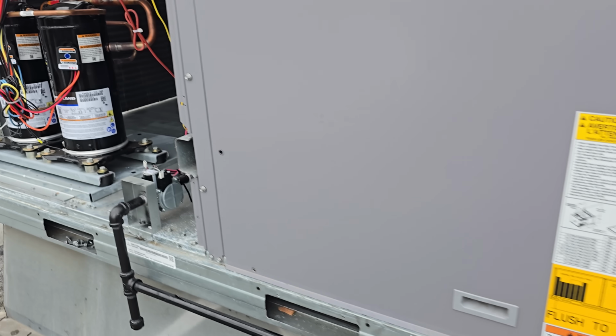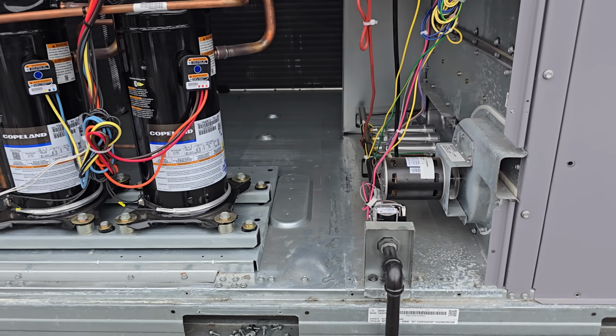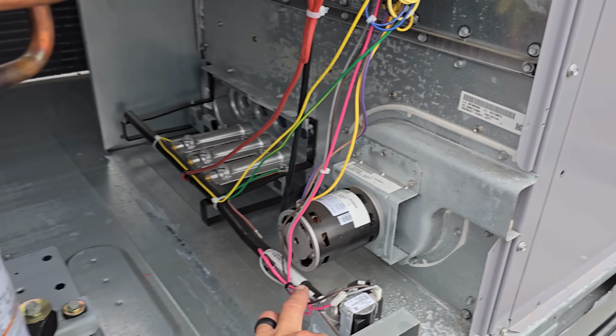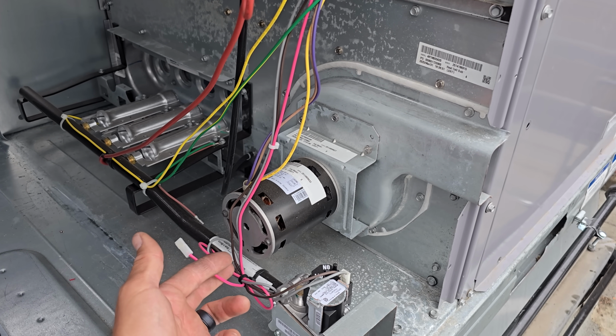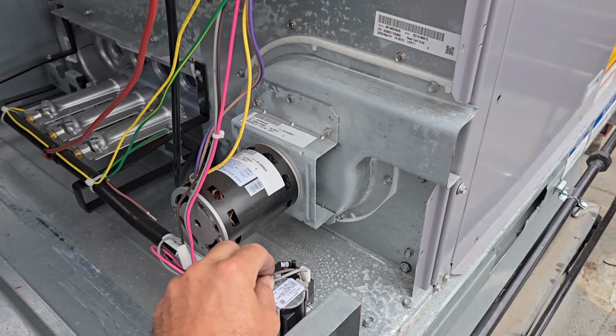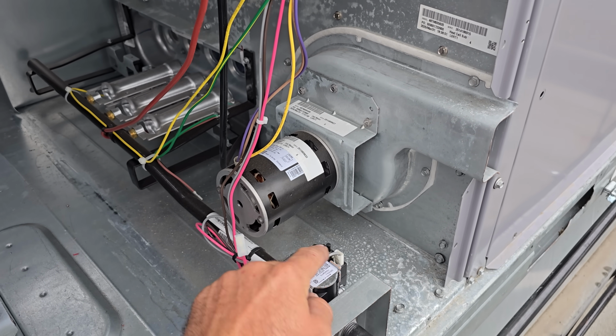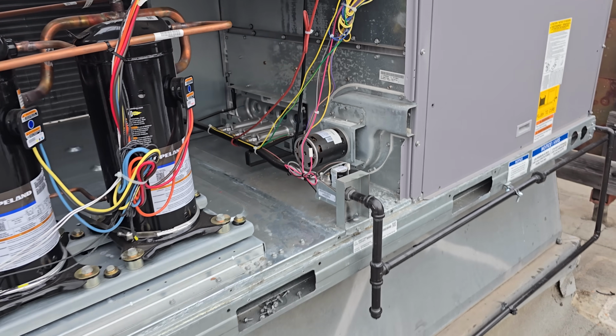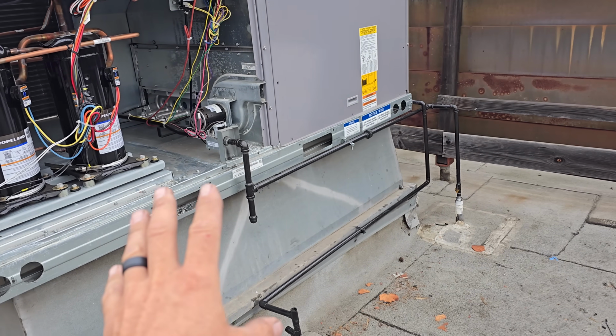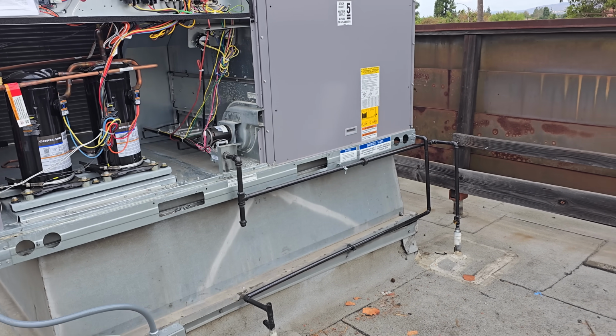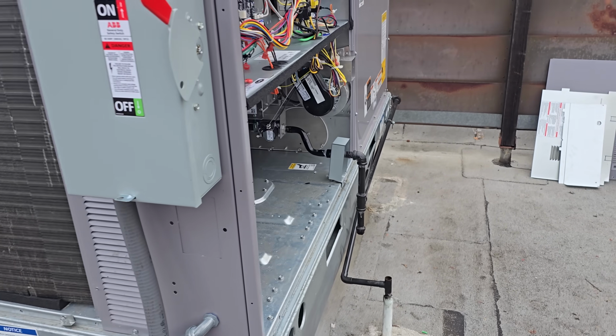We'll start adjusting gas pressures, right? So every one of these units is single stage for gas. You can see the pink wire is not hooked up. There is no spot for it because these are single stage gas valves. So we don't need to worry about the second stage as far as heating goes. So we're just gonna set the gas pressure and then check the temp rise.